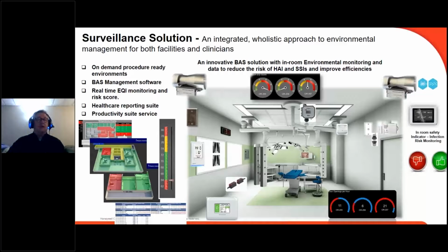It's basically an environmental quality system in which we monitor a number of different environmental parameters. And by monitoring those parameters, we can correlate that back to a microbial load. And that microbial load tells the hospital whether or not the probability of infection risk is high or whether it's low, right? But all that data that we're trending through this sensor suite, we can actually provide to the hospital to do a root cause analysis, provide quality of care information, change their sequences, and have a better, more informed picture to reduce their risk footprint, right?